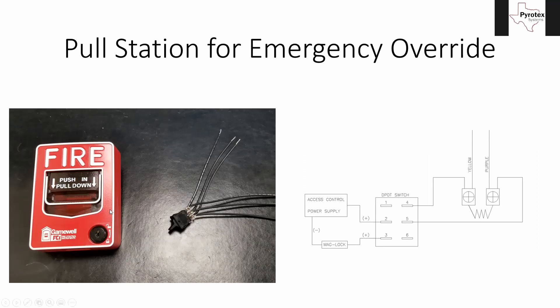A lot of people mistakenly refer to this as a double action pull station, but that's not true. This is a double pull, double throw switch. A double action pull station means you push in and pull down; a single action would only require you to pull down. Double action refers to how the pull station is activated; double pull, double throw refers to what type of switch is inside it.